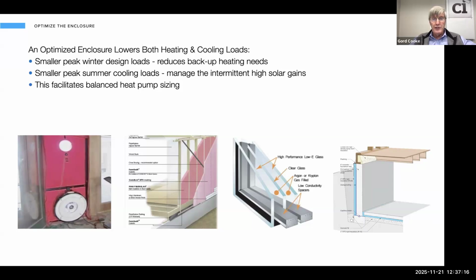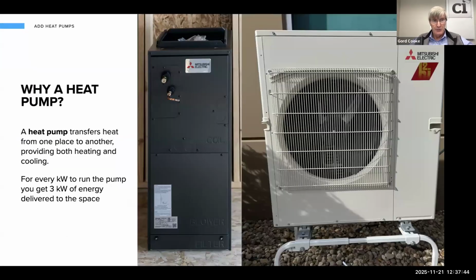When you've managed the heat loss and managed the peak summer gains, that really facilitates the balancing out of heat pump sizing. Minimizing air leakage, improving effective R values, putting in high performance windows, and ultimately full foundation insulation, including under the slab, is really cost effective from a load management and resiliency perspective.